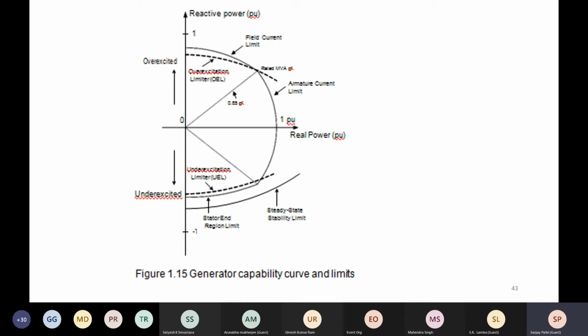So this is, I would say, a 3-stage protection and control. First is the over-excitation alarm, then the AVR over-excitation limiter will come into the picture, and then the manual action, which is to be taken on the grid side, will be taken. So these are the 3 levels of control, and the moment you get an alarm at the first stage itself, you should contact the load dispatch center. Right? Sir, different machines have different characteristics and different capability curves. So how do they decide the MVAR range? This should be the minus range and this should be the plus range. Is there any design aspect, sir?